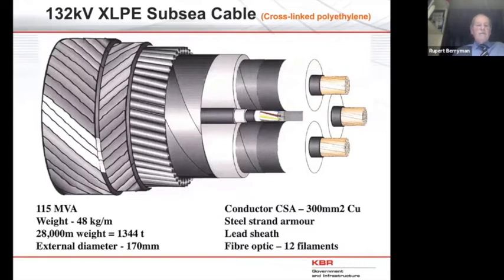Here is a typical subsea armoured cable. This is the 132 kV cable that we used 27 kilometres of to connect Barrow offshore wind farm to shore. Obviously 3 conductors, red, yellow and blue phase for the electricity. Weight 48 kilograms per metre, carrying 90 megawatts or 115 megavolt amps. 28,000 metres, so it weighed 1,344 tons. External diameter is about 170 millimetres. And there's a fibre optic running through it as well for the SCADA system.